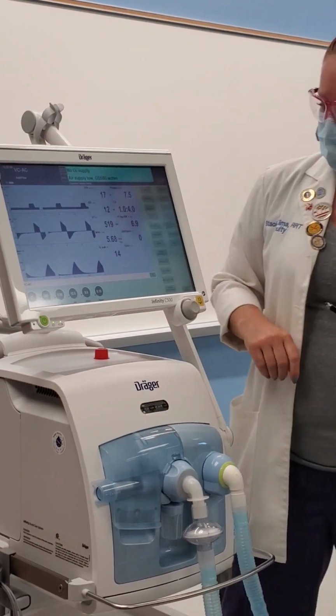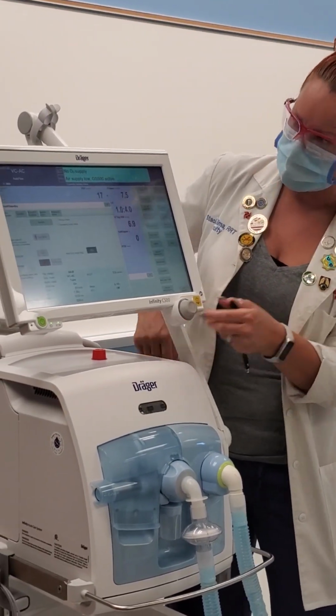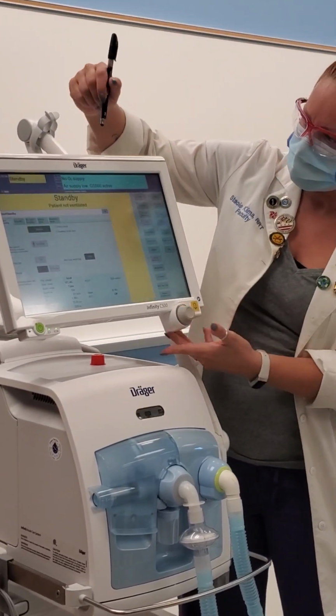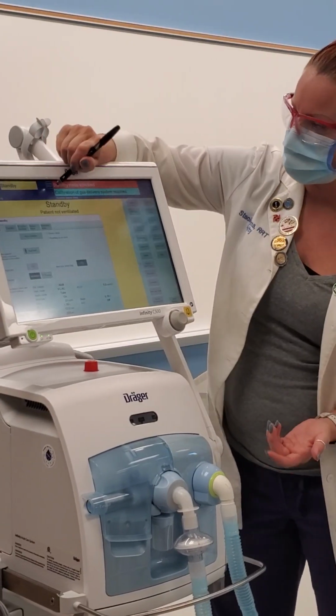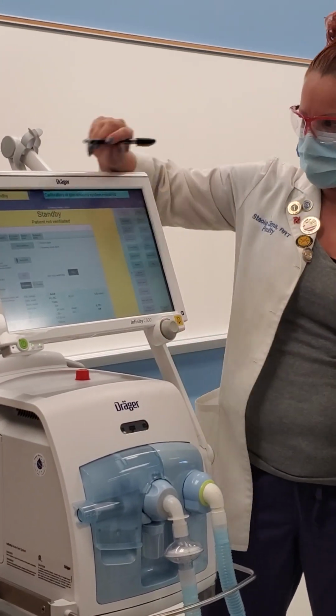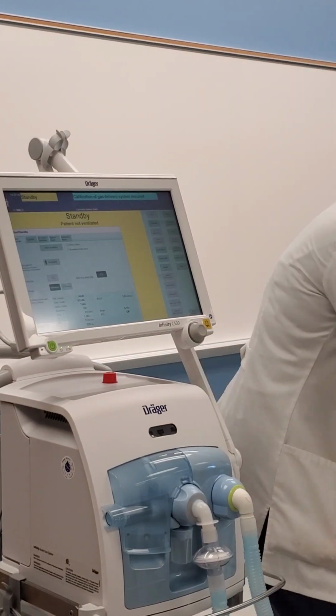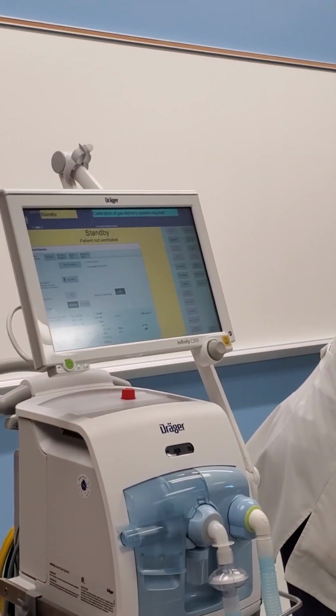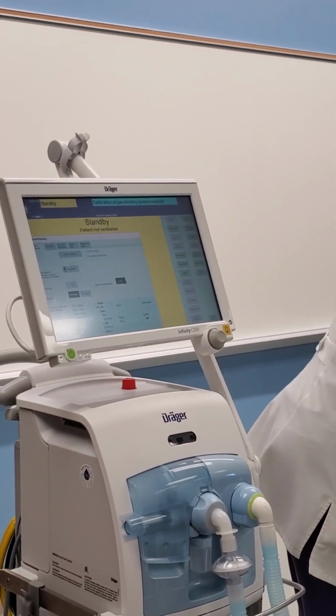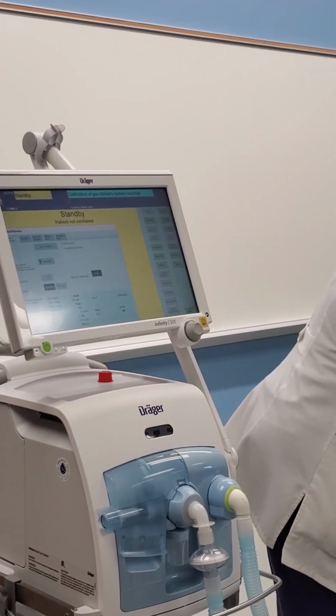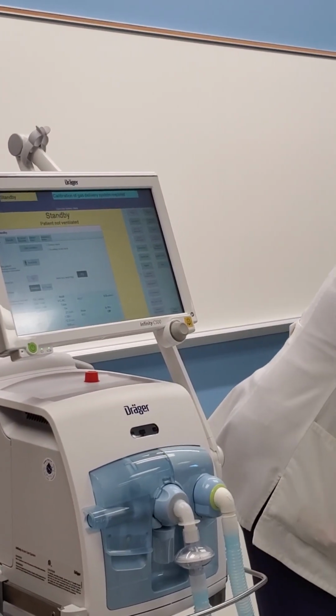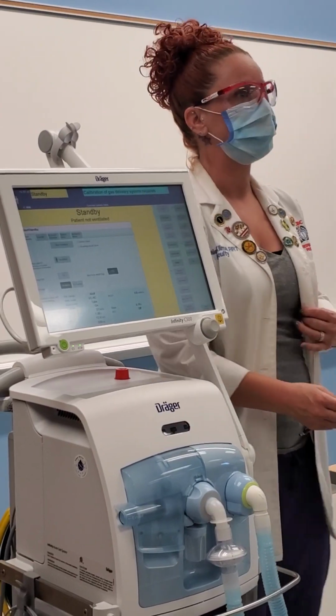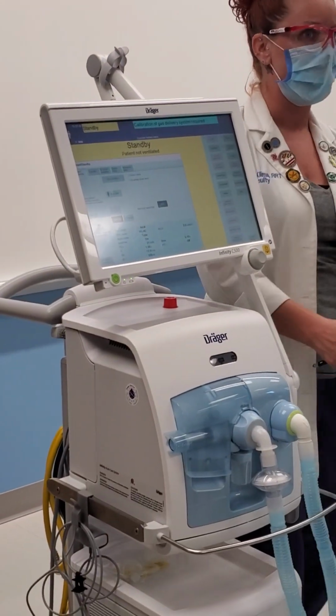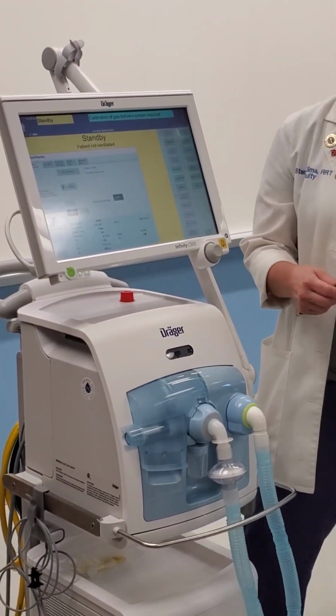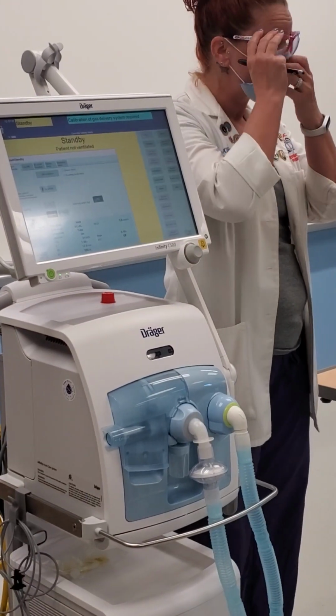To go to start and standby, you have to hit start standby, click, and it's going to alarm again to be like, are you sure you don't want to kill your patient? Hit yes, I'm sure, hit it again, because watch. Nothing. See, the ventilator doesn't recognize it, so be very careful about that. You have to disconnect and either reconnect to whatever you're doing or bag, okay?